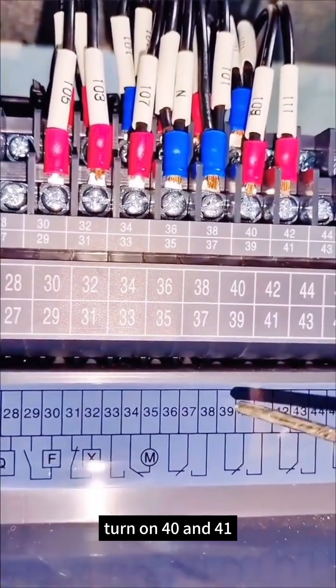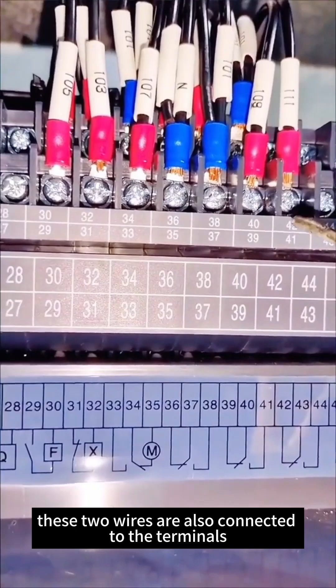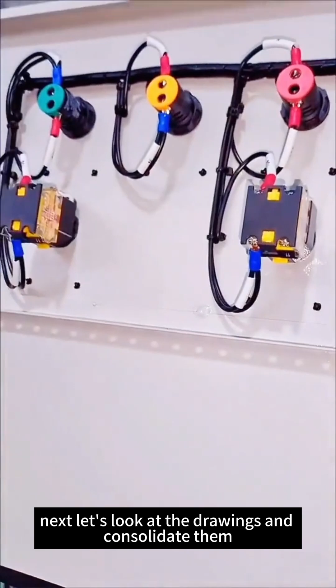Then, after the circuit breaker closes, 40 and 41 turn on as the closing indicator of the circuit breaker. These two wires are also connected to terminals, which transmit to the red and green lights on the panel to indicate the breaker opening and closing. Okay, now let's look at the drawings and consolidate this.